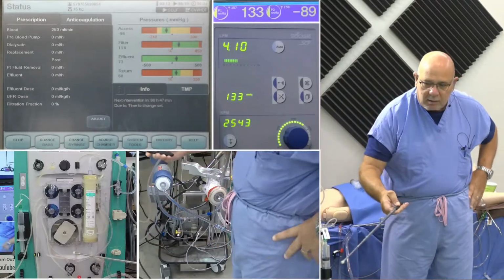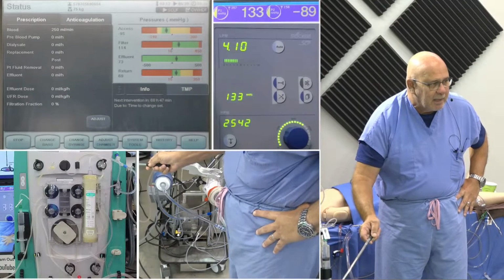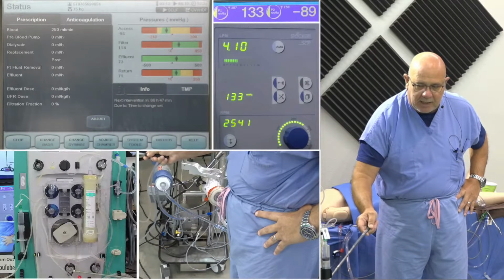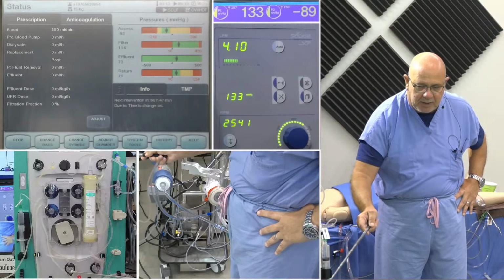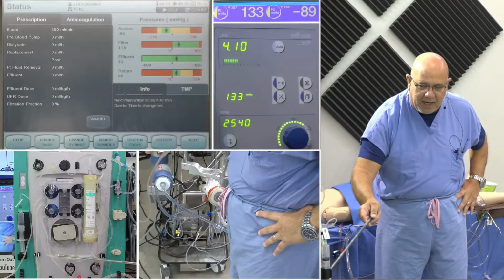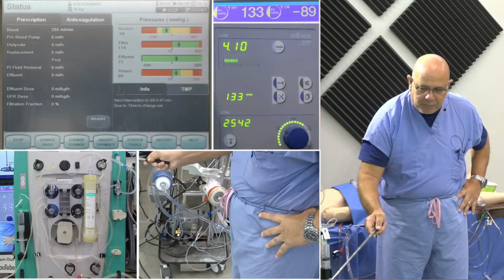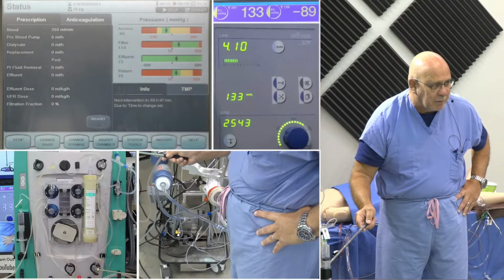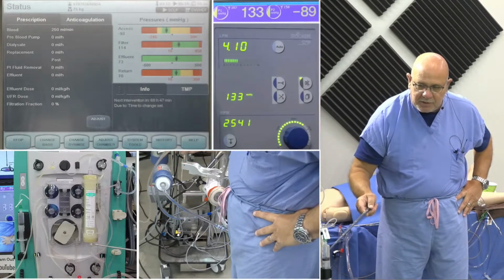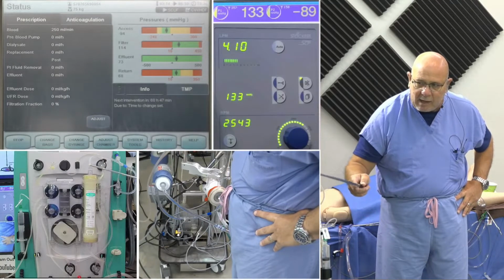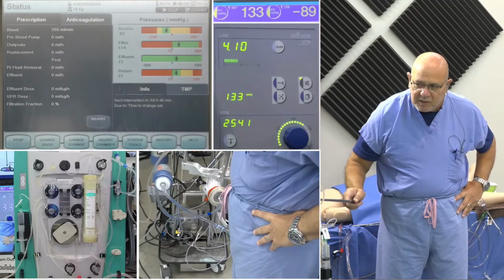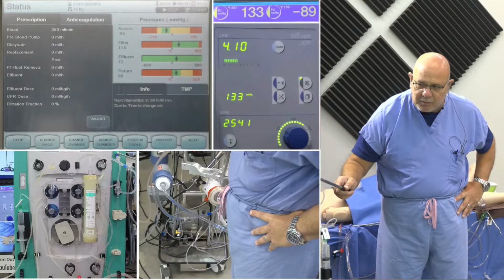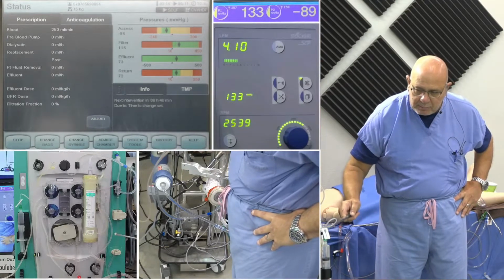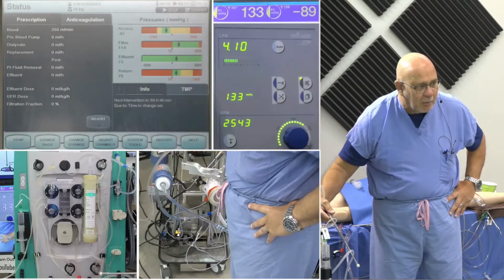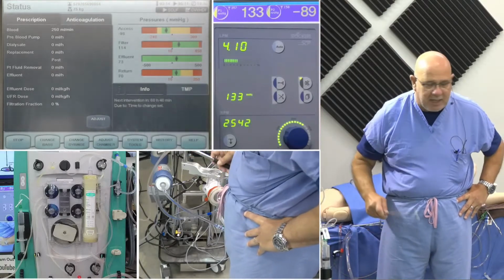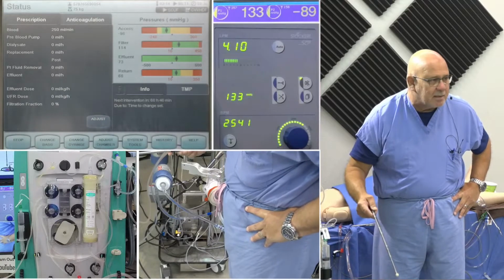So you have our access line, which is the red. It's coming into the access pressure pod here, which is measuring the pressure coming from the temporary dialysis catheter in the patient before the roller pump. So negative side of the roller pump comes around, the blood goes through the filter pressure pod, which you're seeing right here, goes up into the hemofilter, out of the hemofilter, now as you see blue, goes into the deaeration chamber, which is measuring now a pressure here, which is our return pressure, the blue line coming down and out, and then it's going to our simulated patient, which is a saline bag that you can't see. It's off screen. But a very basic system that you see here.